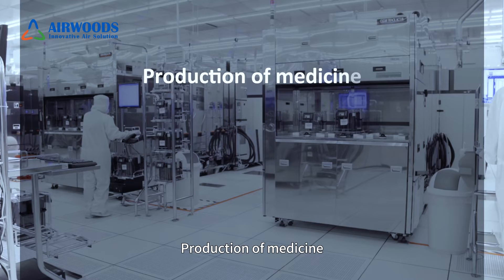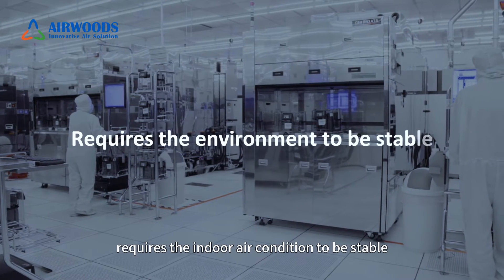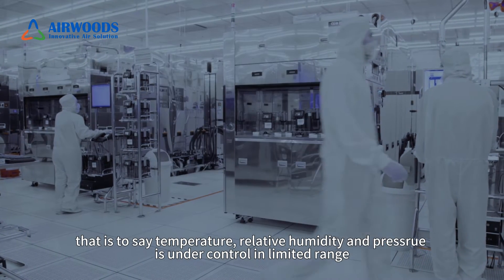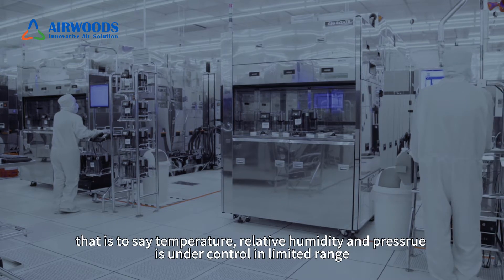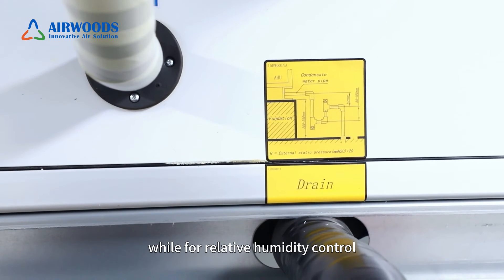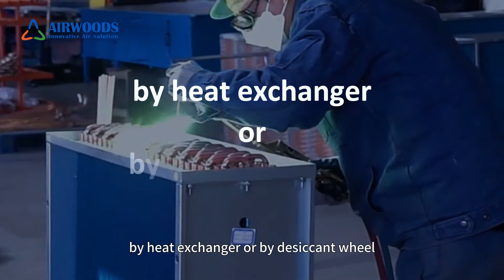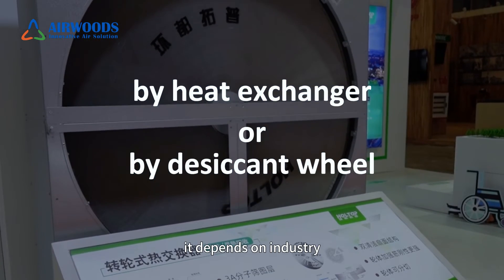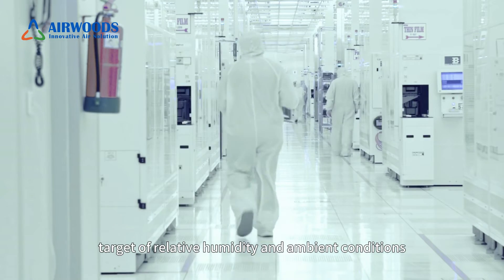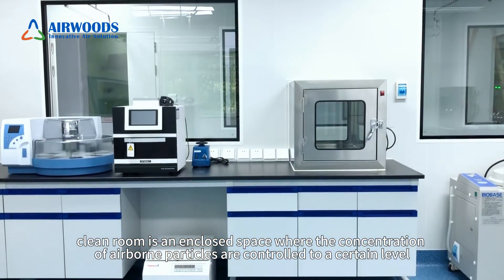Besides being clean, temperature and relative humidity are also important. Production of medicine, medical devices, food, or electronic products requires the environment to be stable — that is, temperature and relative humidity are controlled within a limited range. The air handling unit has a heat exchanger to control temperature. For relative humidity control, there are two options: a heat exchanger or a desiccant wheel, depending on the industry's target relative humidity and ambient conditions.